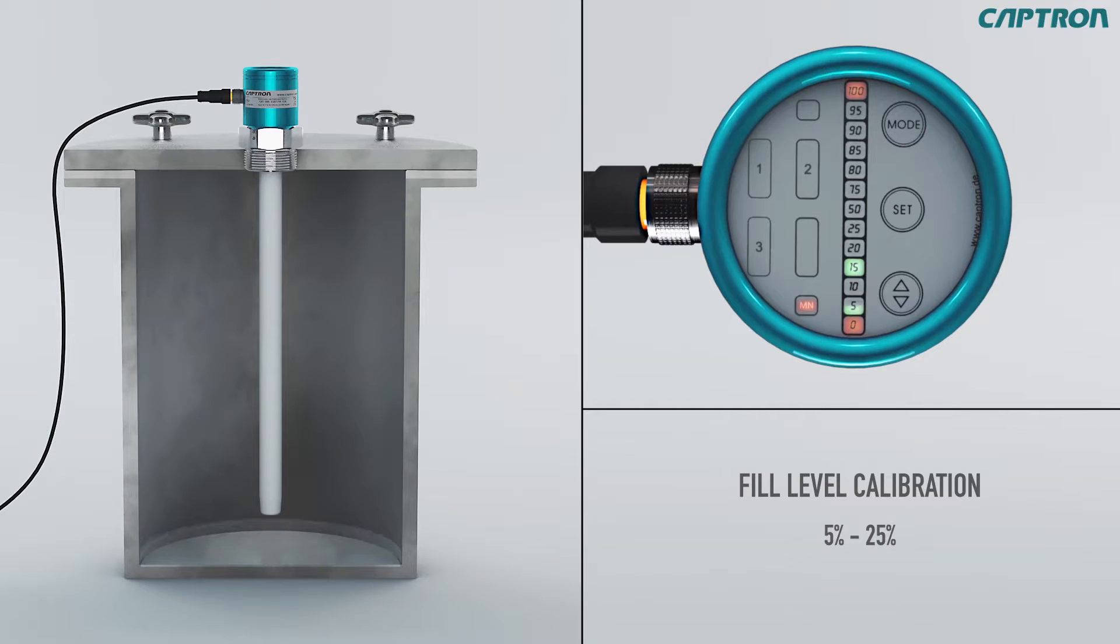Fill the tank with 5 to 25% of the desired measurement range. Now with up down you can set the value which corresponds to the actual fill level. Then confirm the value with set.